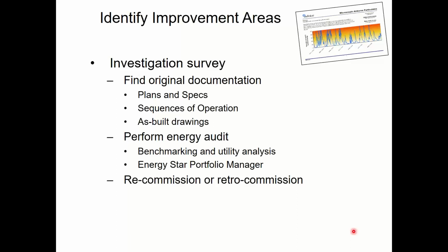It just more implies that it's never been commissioned before, which is very common for a lot of buildings, especially the smaller buildings we're talking about today that have packaged HVAC systems. Somebody threw those systems in, and they tweaked a couple things and they walked away, and nobody really commissioned the whole building. Now, when I say commission, I am referring to it in the modern version with a commissioning authority, somebody who's certified to do commissioning. There's 3 or 4 agencies that certify people.